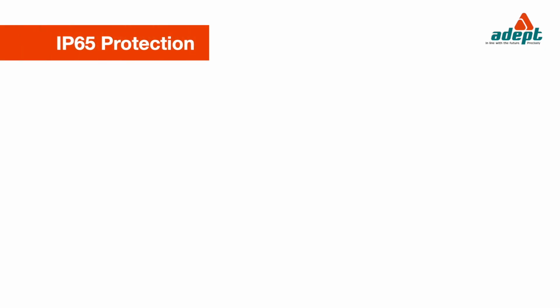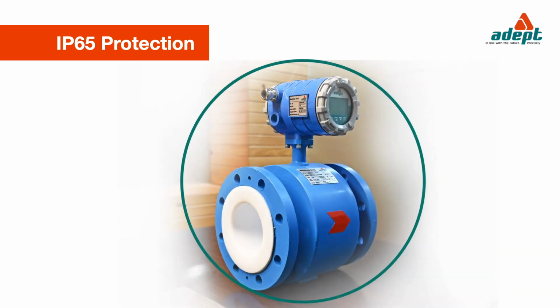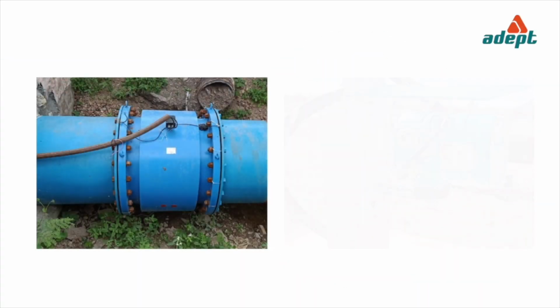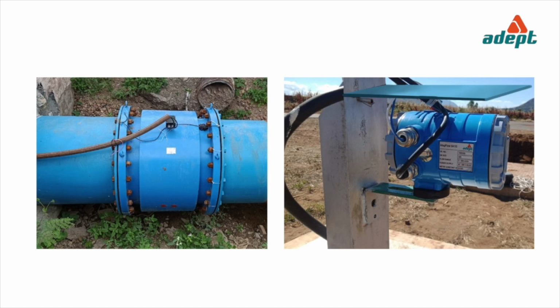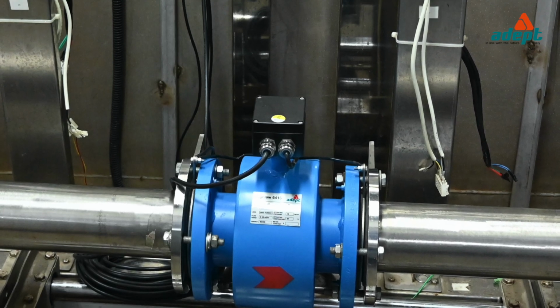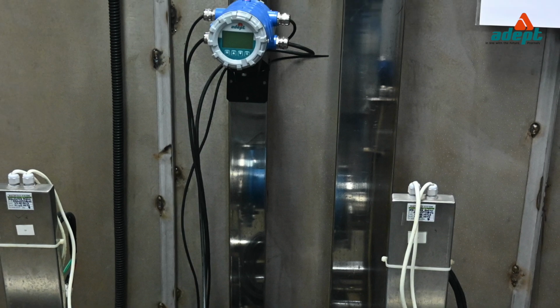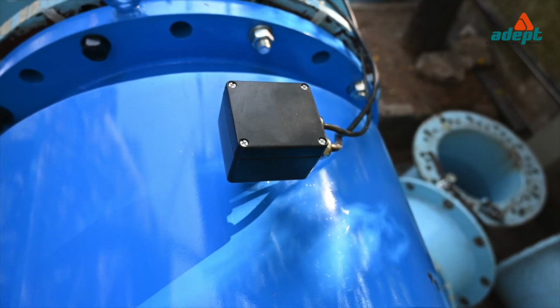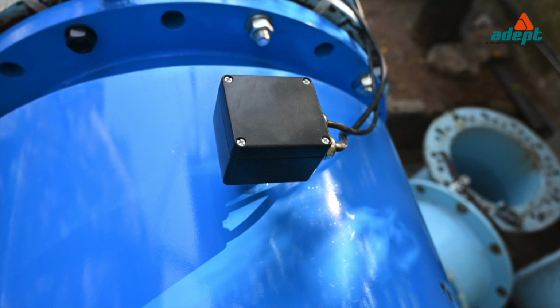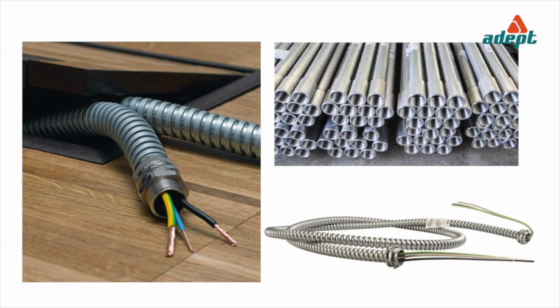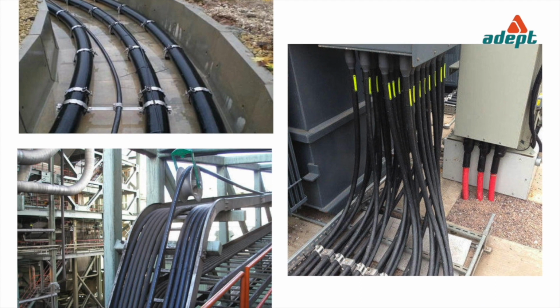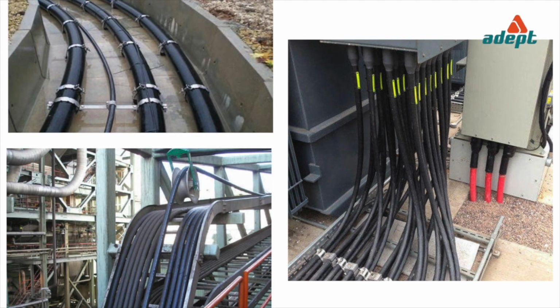The integral transmitter has IP65 protection, and should be installed above ground in a secured location. In case of underground installation, the flow meter should have a remote type of transmitter. The signal and coil cables connecting the transmitter and flow tube are sensitive to electrical noise. It should be ensured that such cables are passed through metal conduits, which are separated from conduits carrying HT and LT power cables.